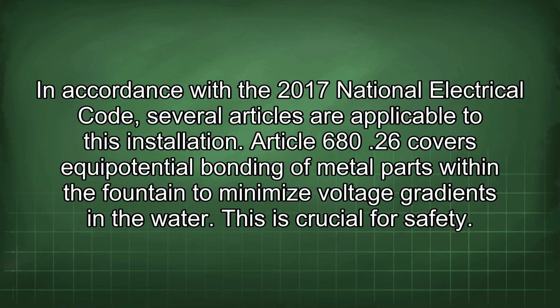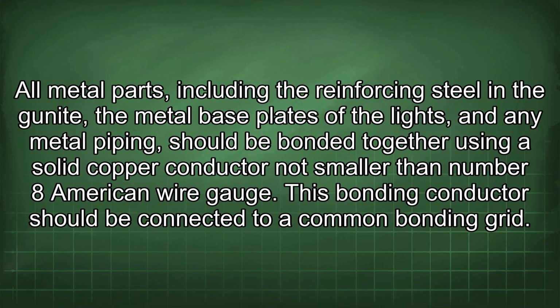In accordance with the 2017 National Electrical Code, several articles are applicable to this installation. Article 680(26) covers equipotential bonding of metal parts within the fountain to minimize voltage gradients in the water. This is crucial for safety. All metal parts, including the reinforcing steel and the metal base plates of the lights, and any metal piping, should be bonded together using a solid copper conductor not smaller than number 8 American wire gauge. This bonding conductor should be connected to a common bonding grid.